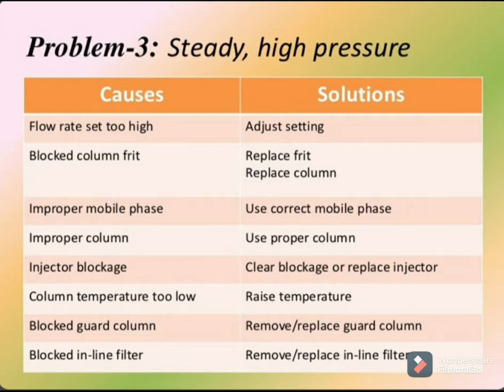Improper column: use the proper column. Injector blockage: clear the blockage or replace the injector. Column temperature too low: raise the temperature. Blockage in the guard column: remove and replace the guard column. Blocked in-line filter: remove or replace the in-line filter.